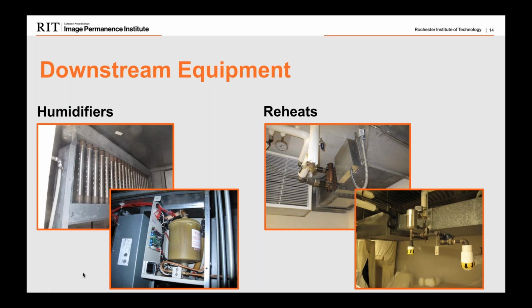If you can't look inside the ductwork, you could look for some signs. This is actually a reheat with a humidifier, so you can see the water lines going to it with this little canister here. And if you can open up, sometimes they're inside a cabinet, so there'd be a canister as well. Just to give you an idea, if you have humidification. The reheats are designed to reheat or tweak the air leaving an air handling unit to try and reach an optimal temperature. So reheats are generally designed per space for a unit, and that'll help you get that air to a specific temperature. A couple of issues may happen with these. We've seen them leak. The source of water, especially in your collection space, if they break, can cause an issue, or failure could result in lack of heat or humidification downstream.